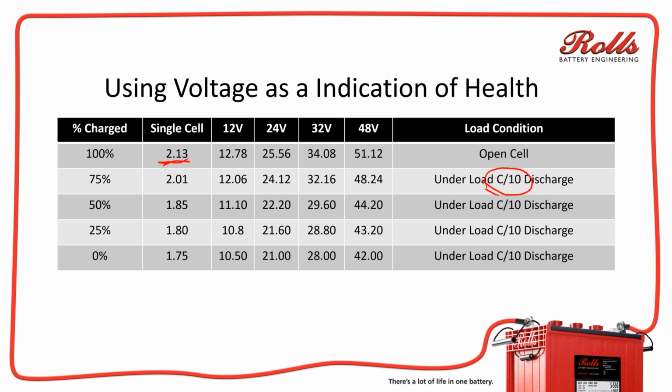When the DC current going to the batteries drops below 10 or 12 amps for an hour, they're not accepting any more current. Then I would load up the battery bank and discharge at about 100 amps, about 10 to 15%, and then charge it again. I would repeat that about 4 or 5 times as I'm commissioning the battery bank.